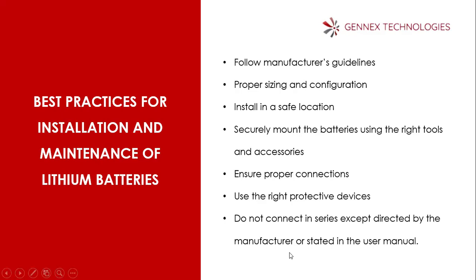Now, proper sizing and configuration is very important. You need to know your design. Don't put a battery rated 10 kilowatt hour on a 10,000 watt load, think about that. A 10 kilowatt hour battery at 48 volts can only support a 1,000 watt load for 10 hours. When you increase the load, which is an advantage of lithium, say the battery can handle higher load, you increase it to 2,000 watts, the backup time will reduce, but the battery won't get damaged because it's still within capacity.